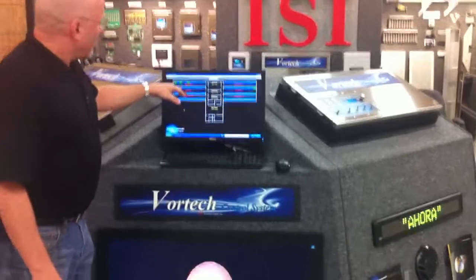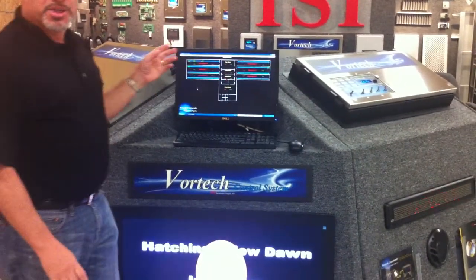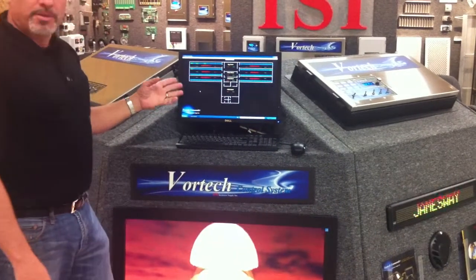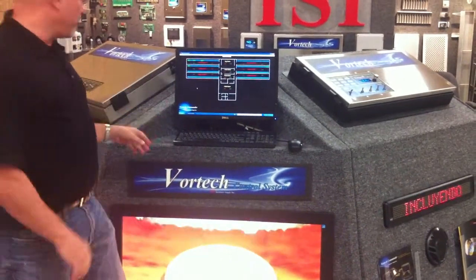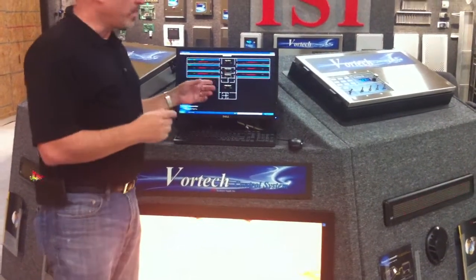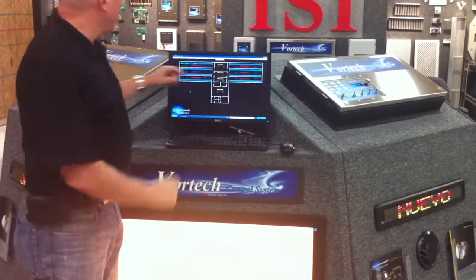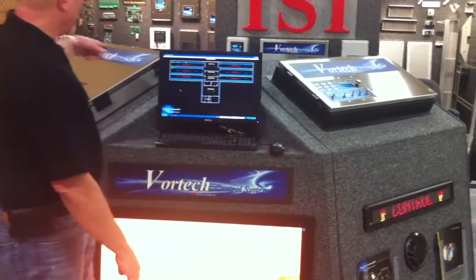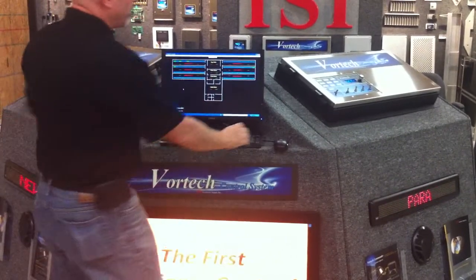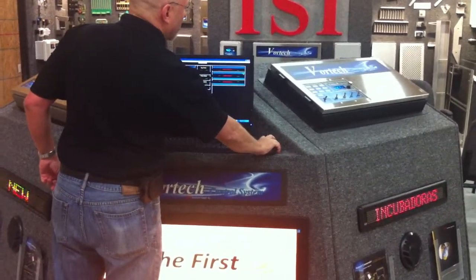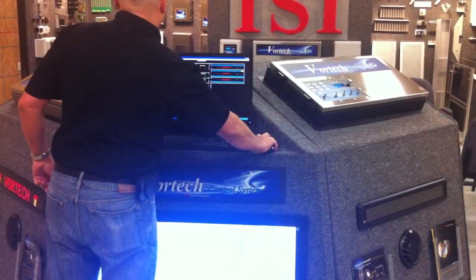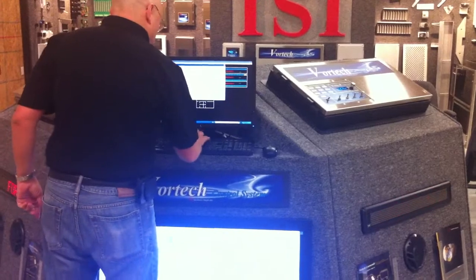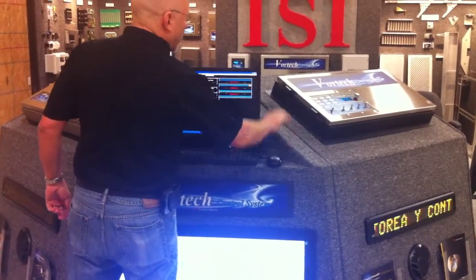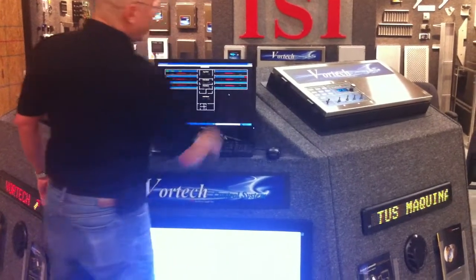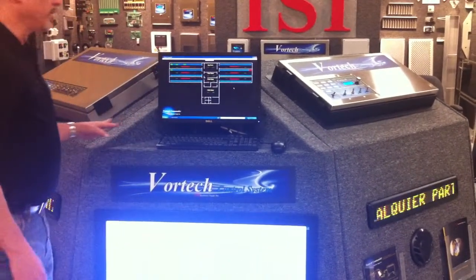What you're looking at here is each one of these little blocks. If it's blue, it means the machine is not communicating. If it's green, the machine is communicating and there are no alarm conditions. If it's red, it means that there's an alarm condition. So all these are blue because they don't exist. These machines we have running here are actually green. I'll create an alarm condition on this machine over here by changing the set point to something out of range. Let's just say 7 degrees. Okay, now you can see that machine's alarming, and it comes up red on your display.